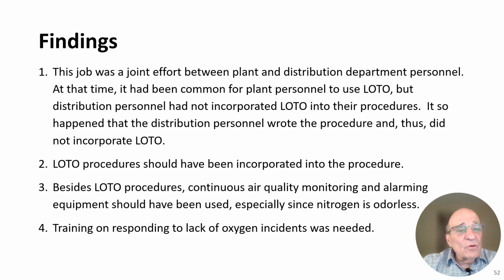It was about 50 years ago, I'd say, that this particular accident happened. This job was a joint effort between plant and distribution department personnel. At that time, it had been common for plant personnel to use lockout, tag out, but distribution personnel had not incorporated lockout, tag out into their procedures. It so happened that the distribution personnel wrote the procedure and thus did not incorporate lockout, tag out. The lockout tagout procedure should have been incorporated into the procedure.